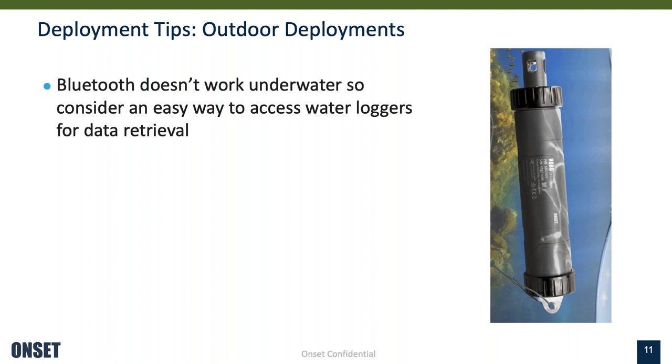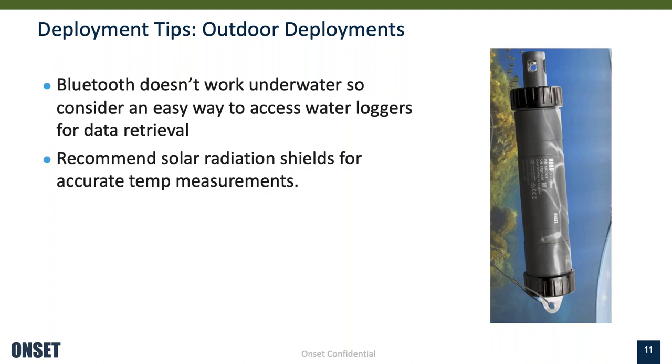And a few deployment tips for loggers that are used outside and underwater. One big point here that we get asked quite a bit in the support department is Bluetooth. Someone might call in and say they can't connect to their Bluetooth logger while the device is deployed. One of the first questions we ask, of course, is whether that device is deployed in a stream or underwater. The reason is that Bluetooth is an RF frequency, and it will not transmit very far underwater. So keep that in mind when you're deploying these devices. You may want to keep them in a place that's easily accessible so that you can remove the loggers from the water, download the data quickly, and then place the device right back where it belongs. So, yep, just keep that in mind.